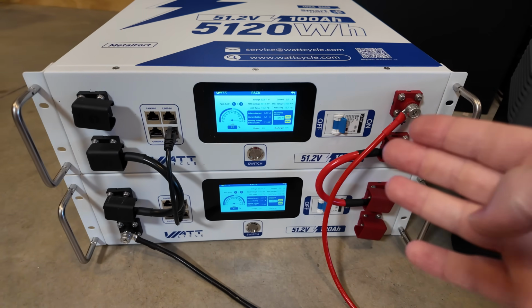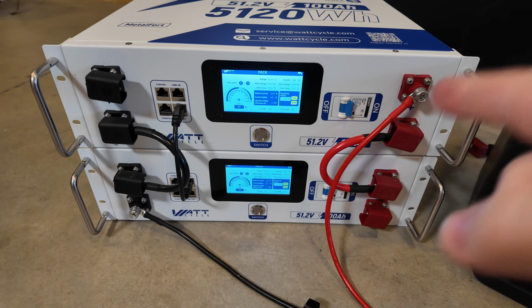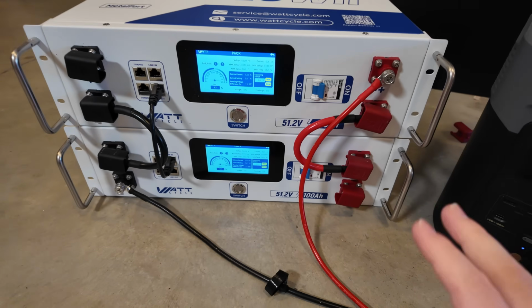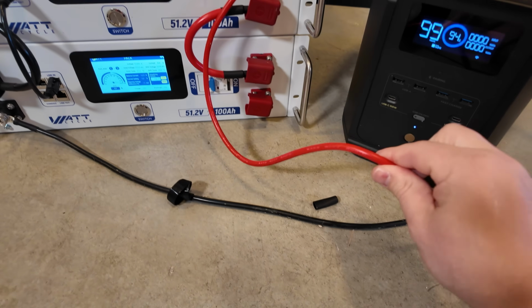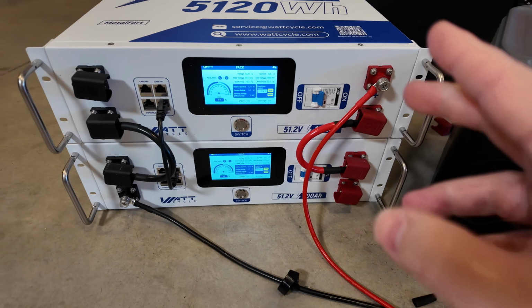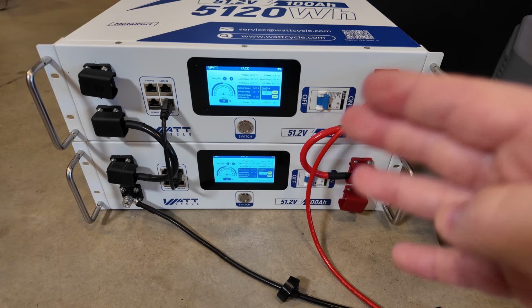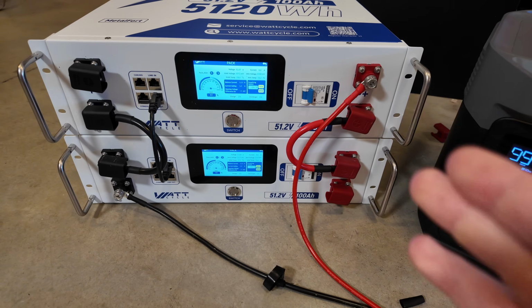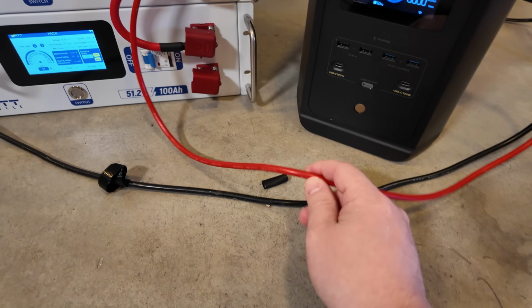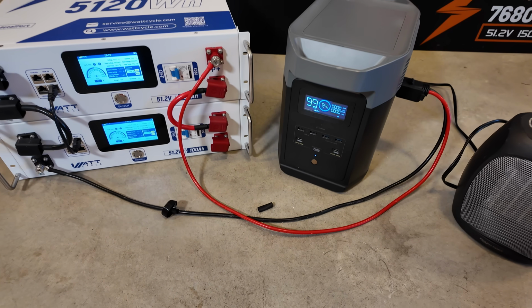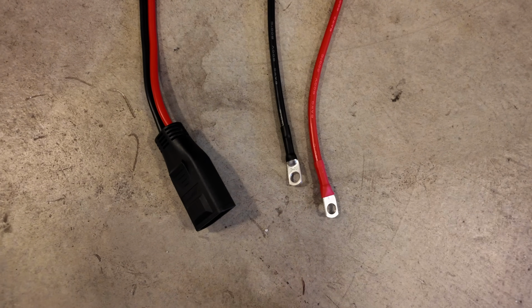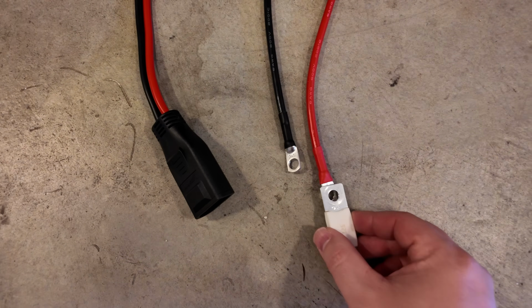If you pair up extra capacity of power, like I'm doing with these server rack batteries, and let's say we had a short with 100 amps going through this cable, each battery is only going to see 50 amps. So they just keep dumping power because it's within spec, and you could have a serious melt or fire issue.